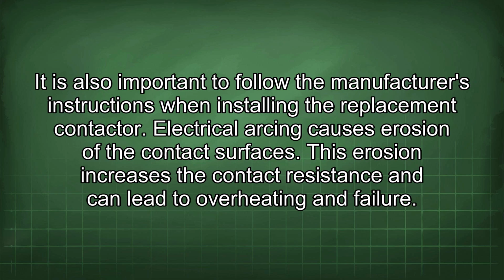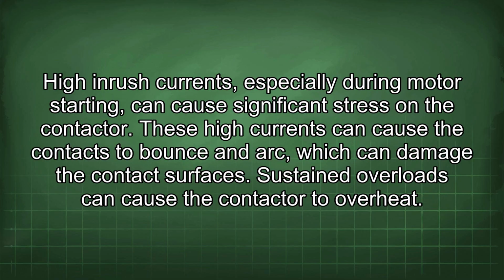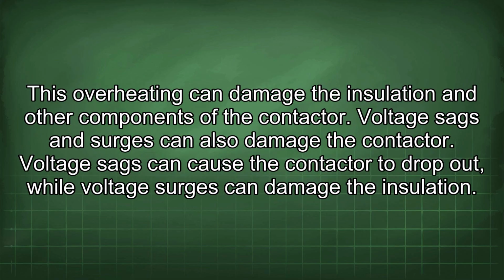Electrical arcing causes erosion of the contact surfaces. This erosion increases the contact resistance and can lead to overheating and failure. High inrush currents, especially during motor starting, can cause significant stress on the contactor. These high currents can cause the contacts to bounce and arc, which can damage the contact surfaces. Sustained overloads can cause the contactor to overheat. This overheating can damage the insulation and other components of the contactor.